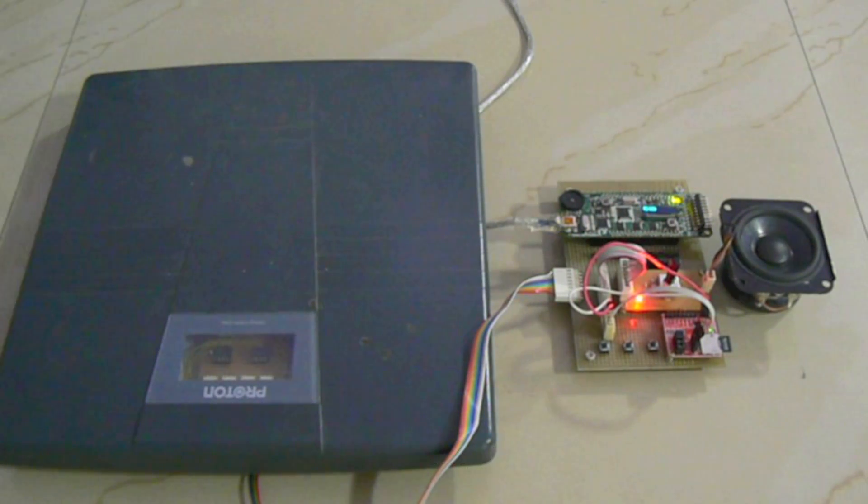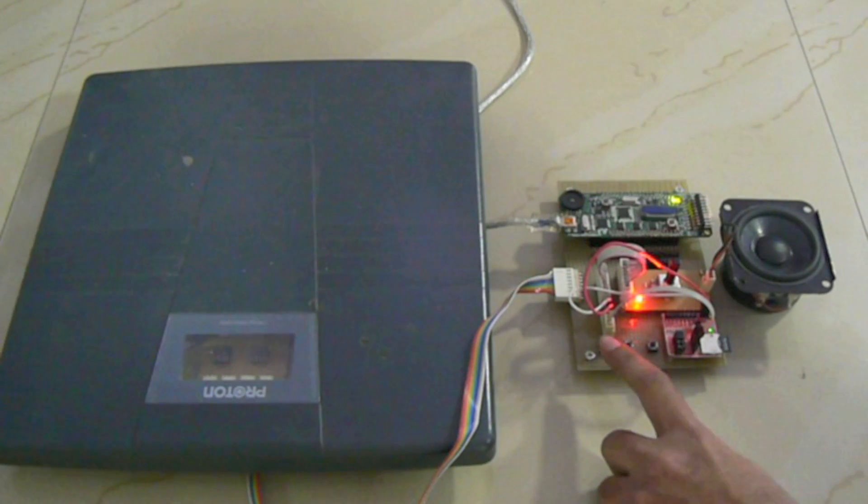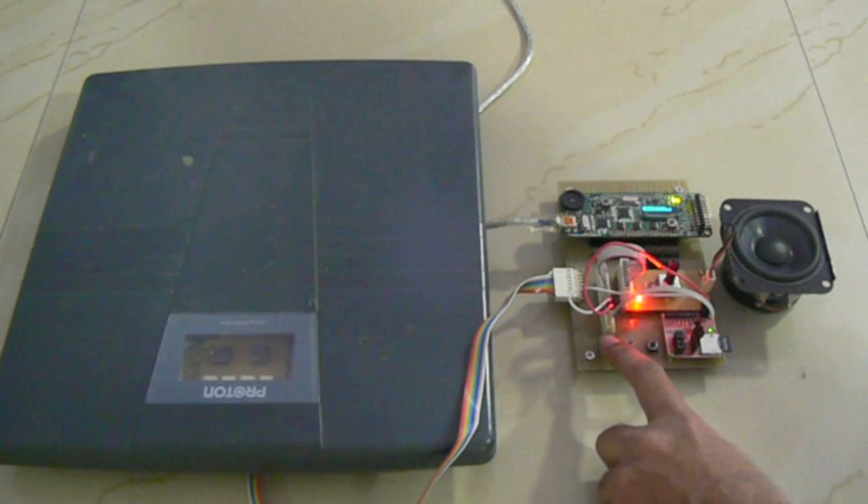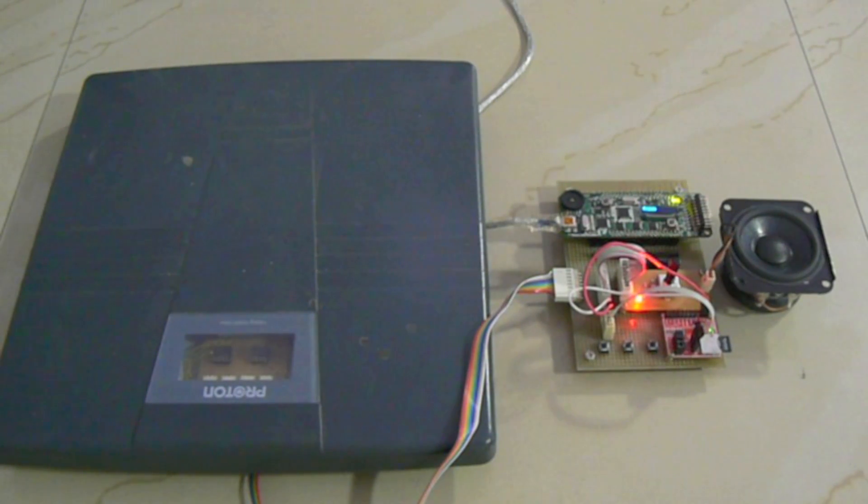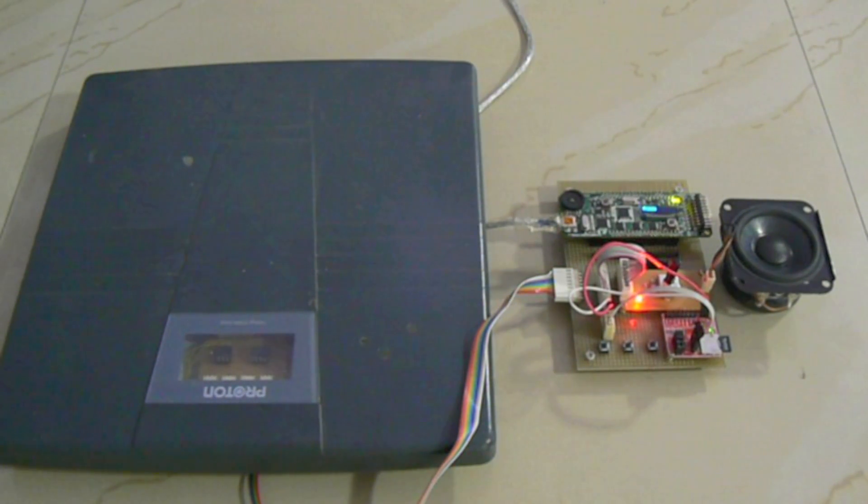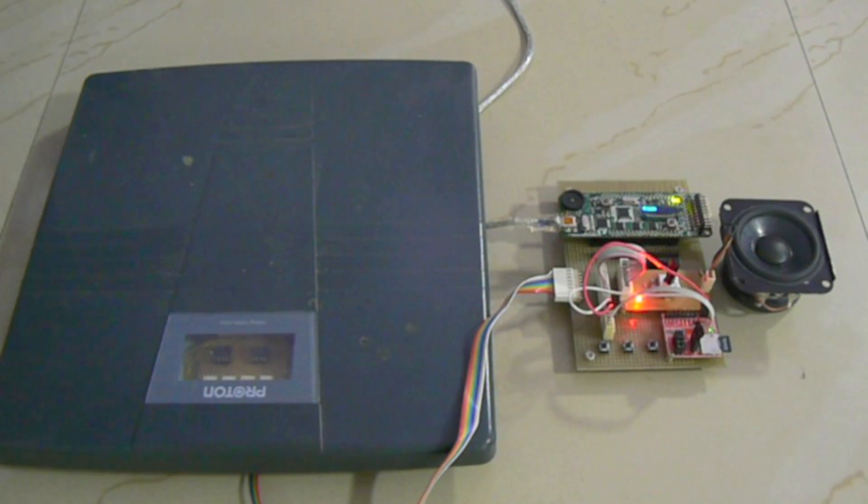The user language can be selected by pressing the left most user button. Pressing it once selects the user language as French. Pressing it many times can be used to switch between multiple languages which can be both Indian and foreign. Now when the user stands again on the scale, the weight readout is in French.